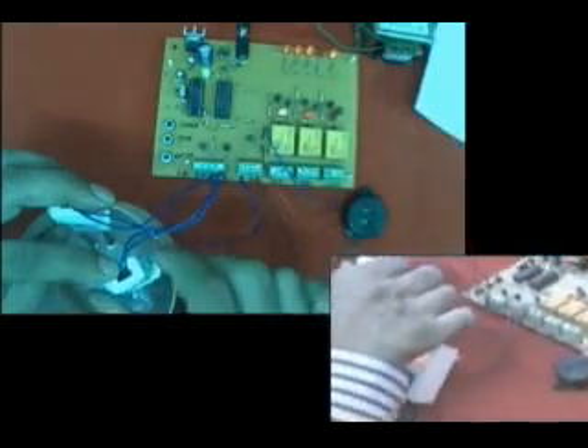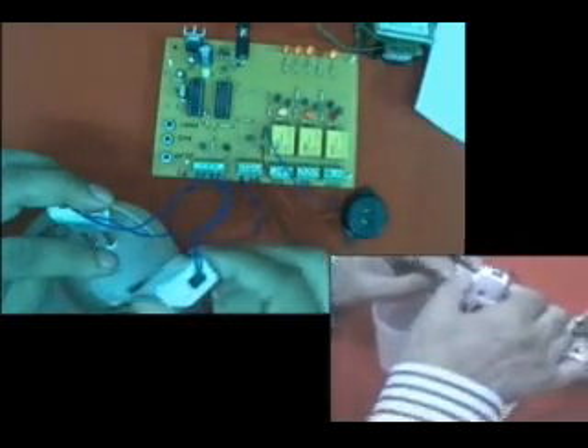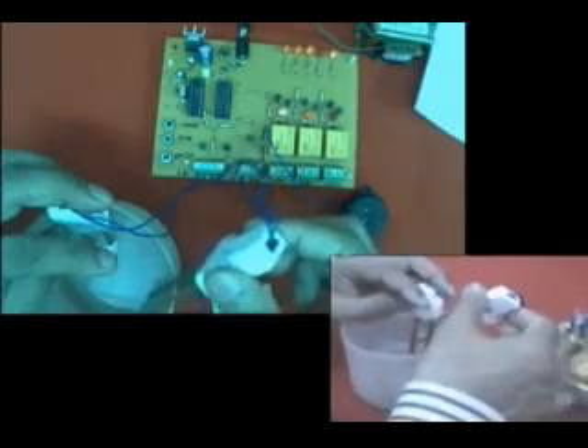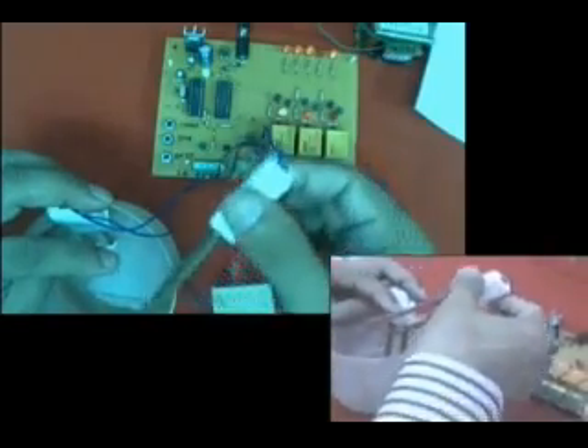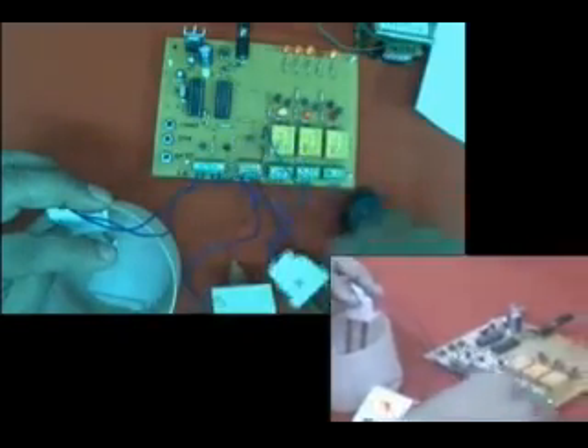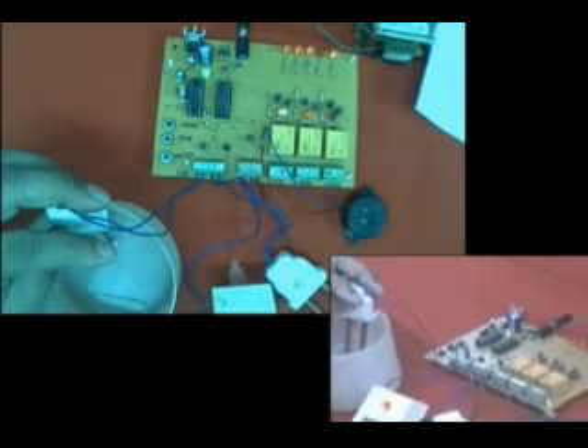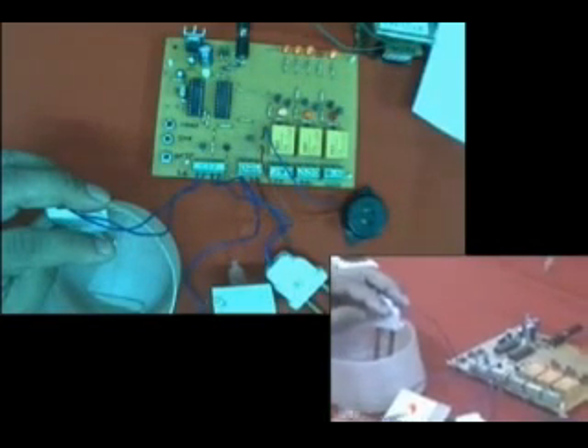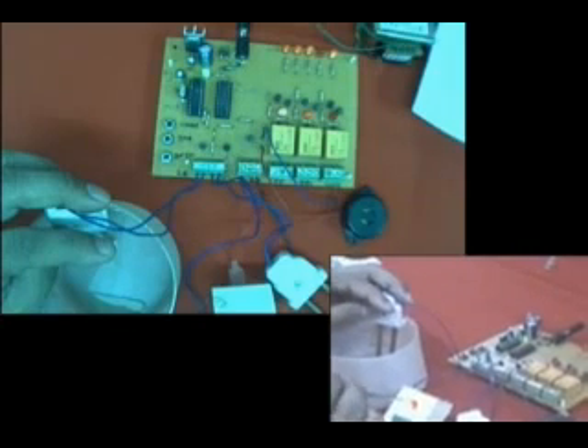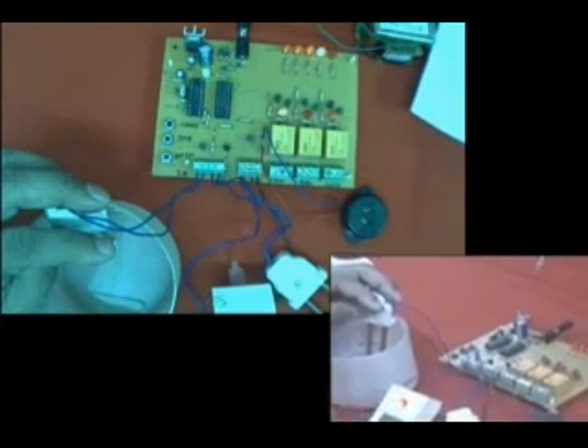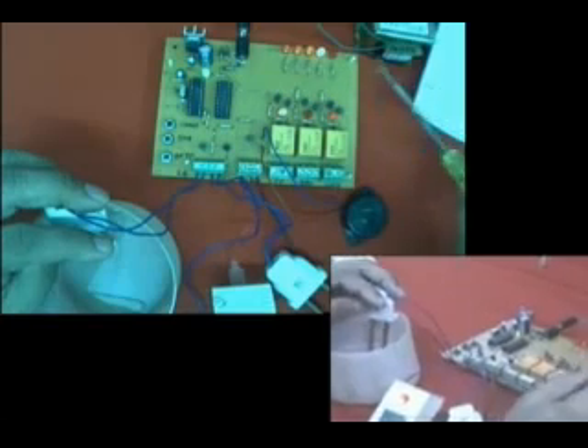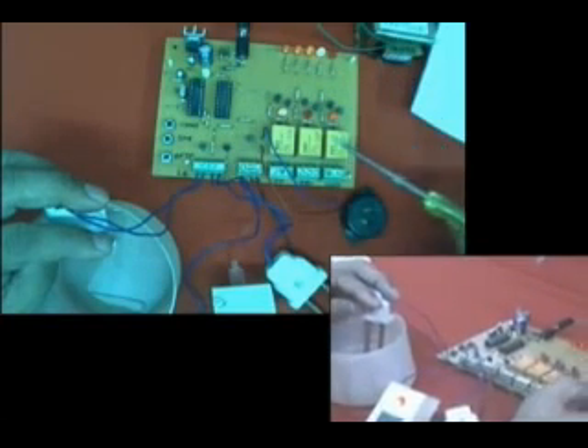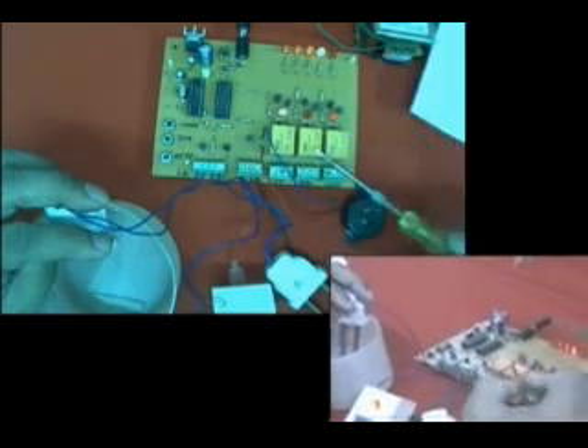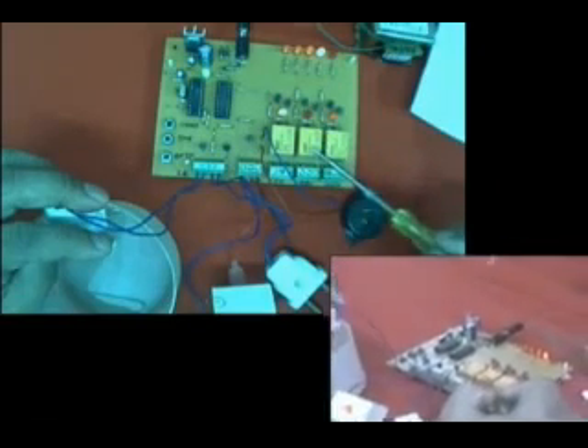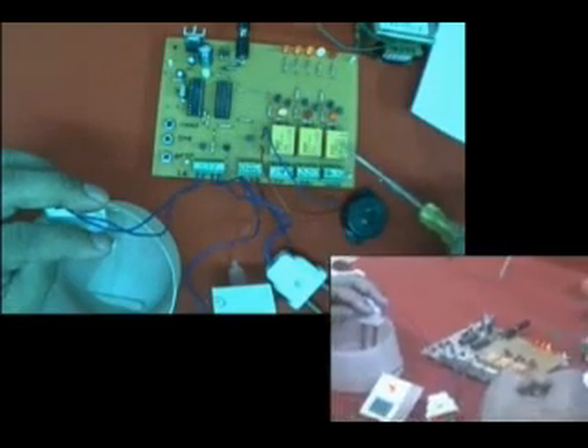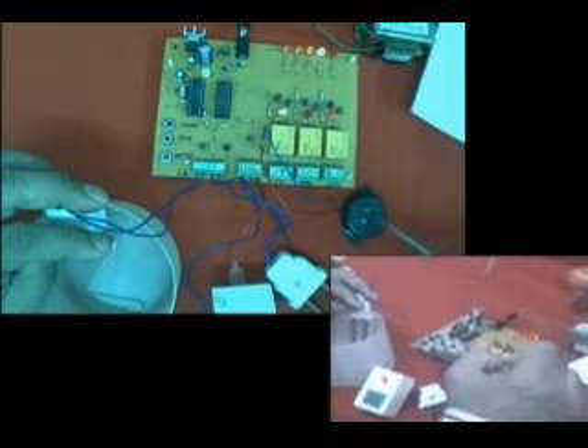After that, the water recedes and comes down. So the water has come down, so we have removed this high level probe. But suppose while pumping out it encounters oil. So we'll put some obstacle here in the oil sensor. See, the same thing is being repeated, but now in auto mode. The overboard valve is shut and the waste oil tank valve is open, and there is a siren for 1 minute.